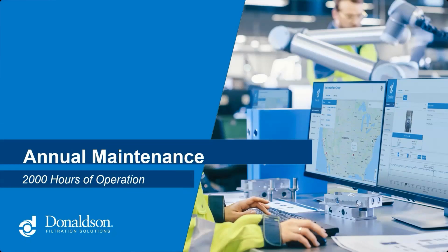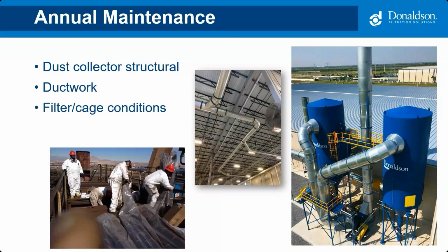Then lastly, what do we do once a year? Once a year is a good time to do a structural check of your dust collector. So you're looking at the overall metal housing of the collector itself, the leg pack that's holding the collector up, as well as just the metal housing itself. You want to make sure it's in good condition. You know, dust collectors are a big industrial asset. They last a long time. So as time goes on, these inspections become more and more important.